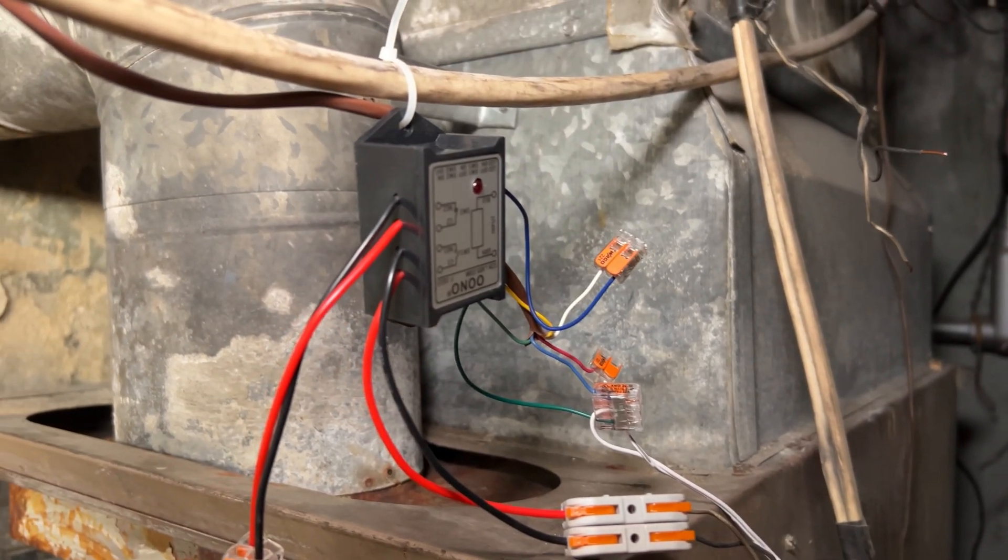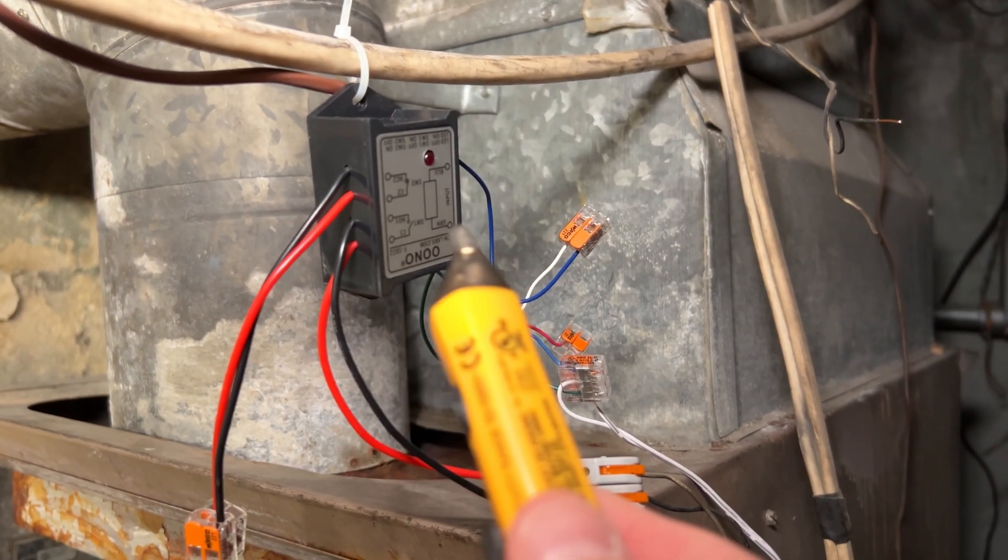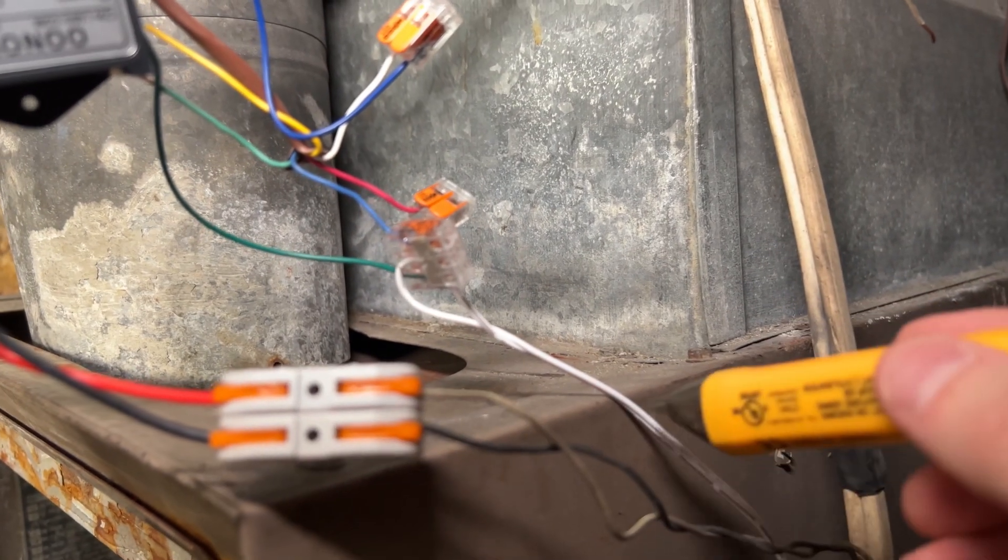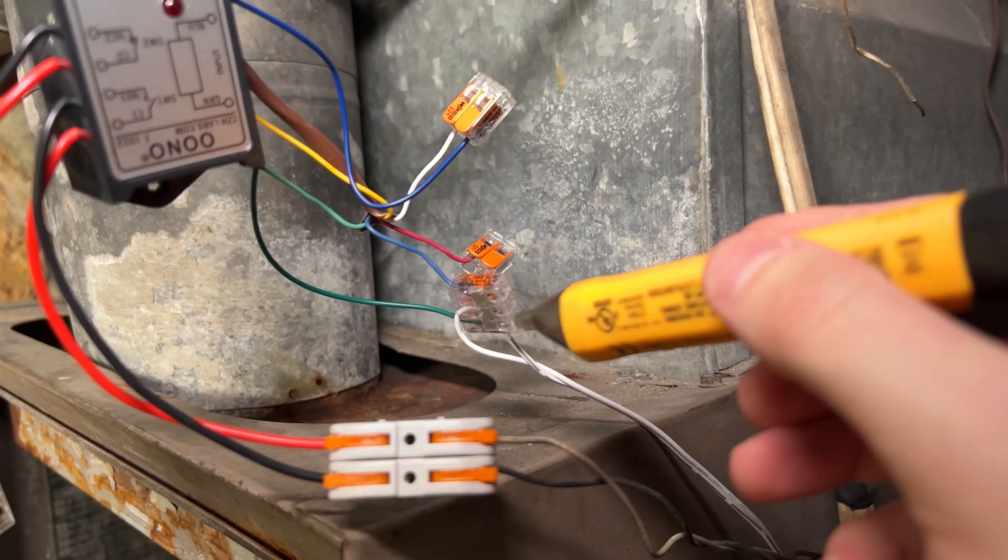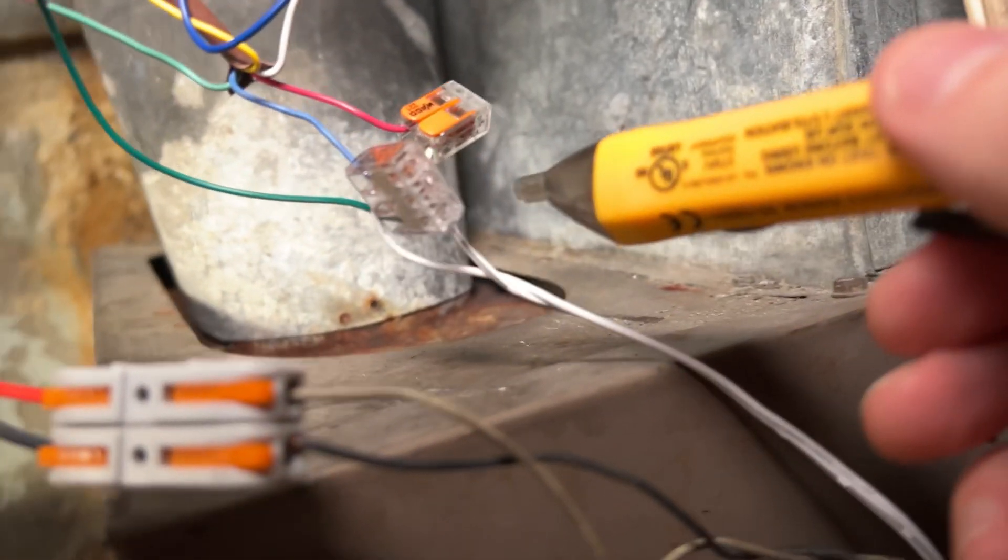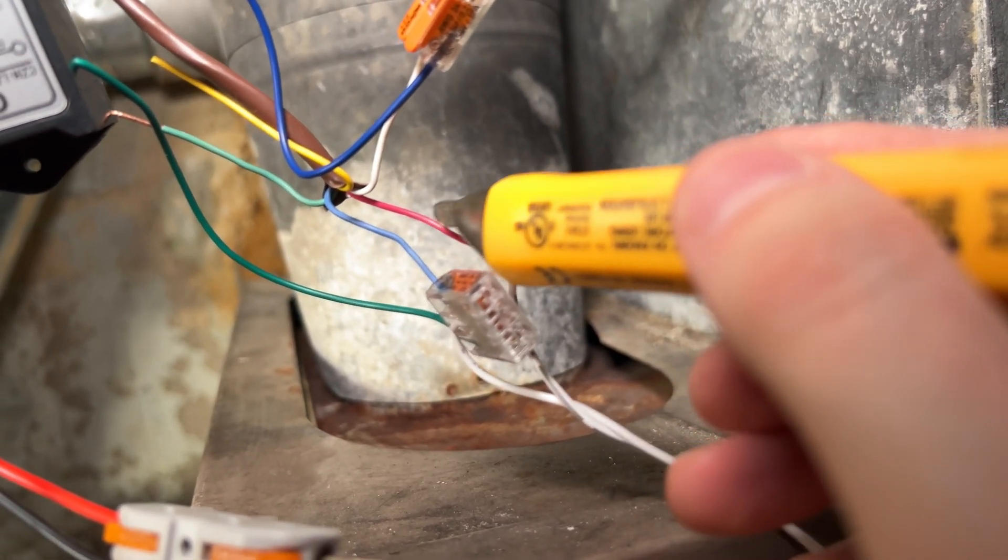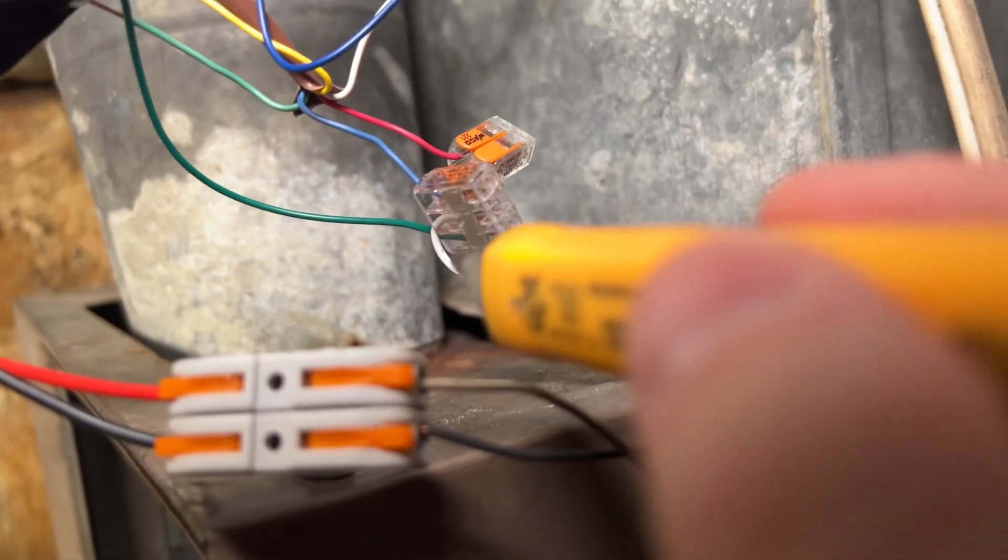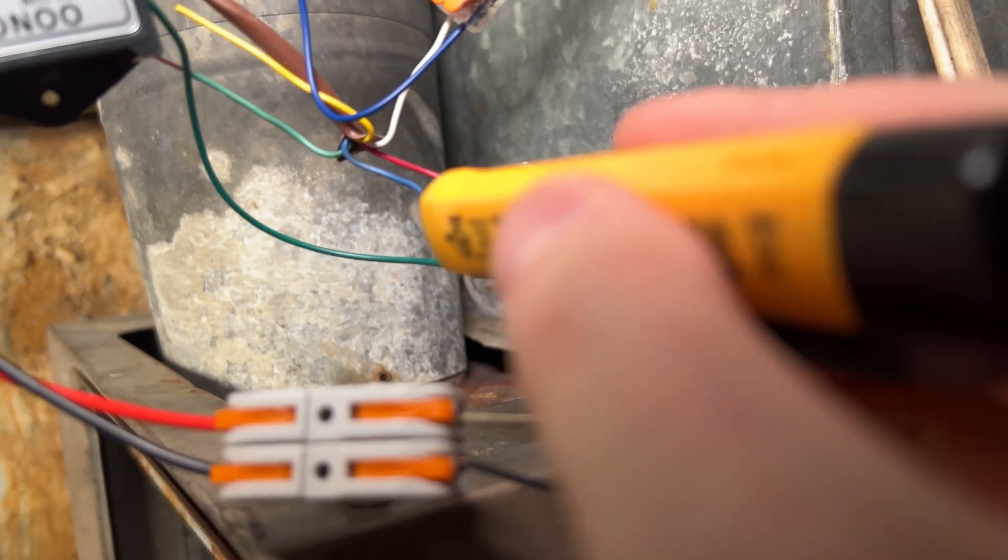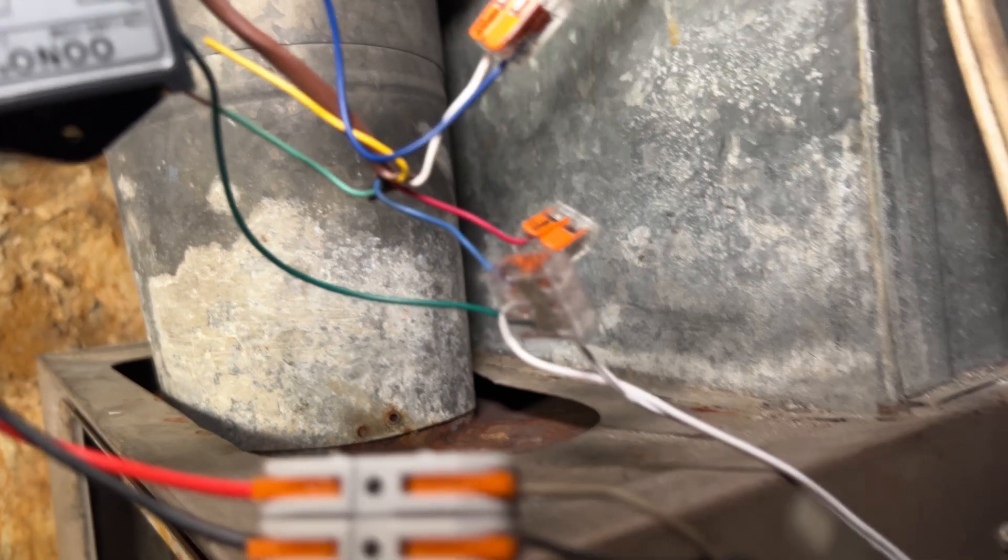And to make it work with our equipment, in this case the furnace, we're using this device called a relay. And the way it's wired is pretty straightforward. So here's our incoming power, this white wire here, and we have one side of the white wire going through this Wago directly to the red wire which is R on our thermostat. The other side is actually being split and one leg is going to the blue wire or the C on our thermostat, and then the other side is going to the relay, that's the green wire here.